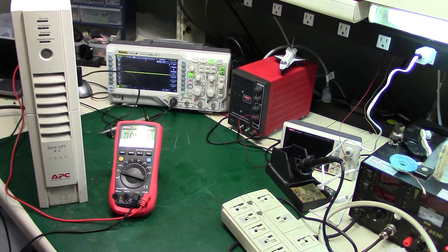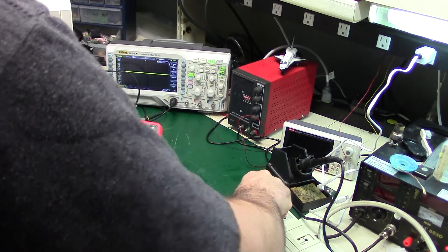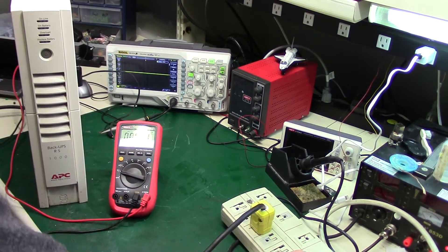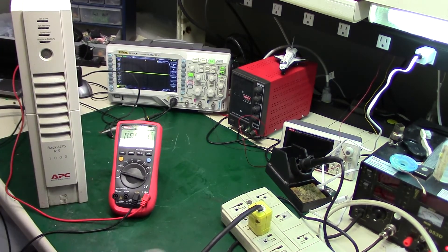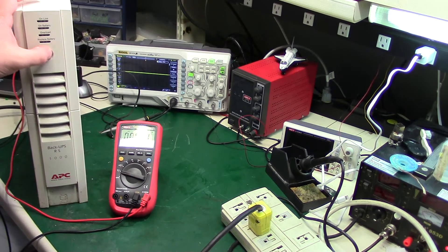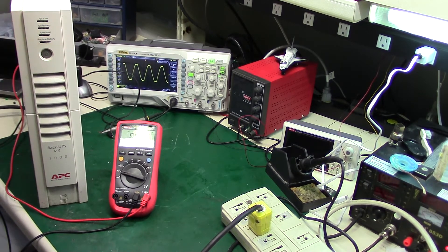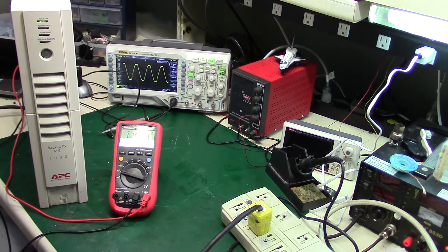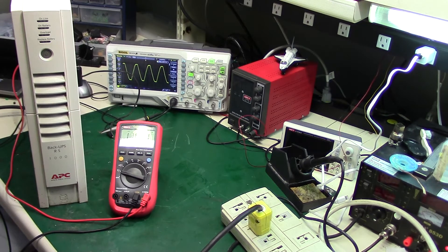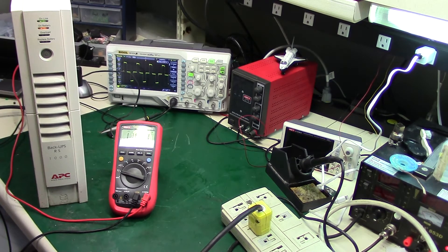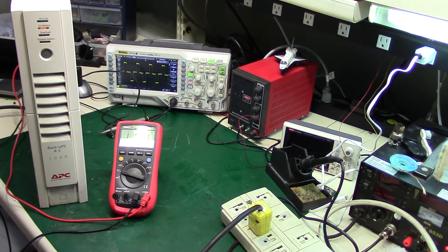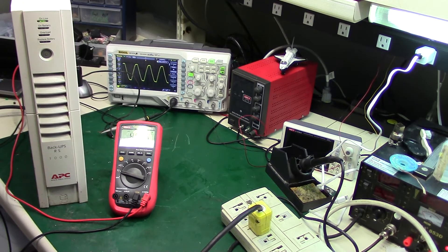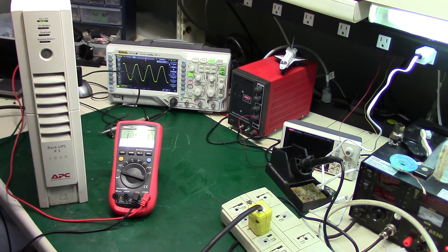Okay, mains power. Turn that on. You should hear some clicking. Okay, let's try to turn it on. There we go. We've got the pure sine wave from the power company, and we'll run the self-test. Okay, it goes to modified sine wave. Oh, what a great looking square wave there. And there we go. We're back to pure sine wave switched right back.